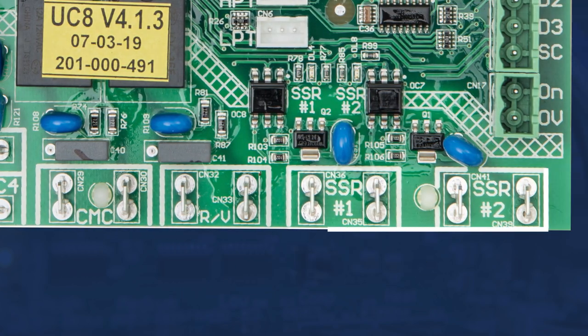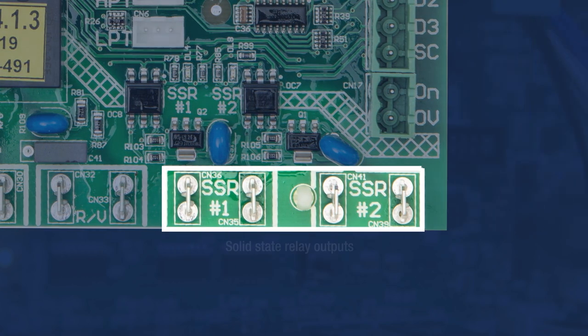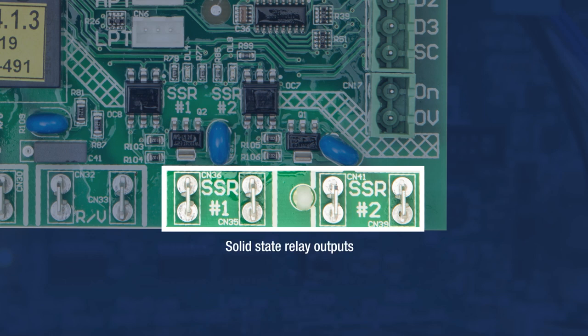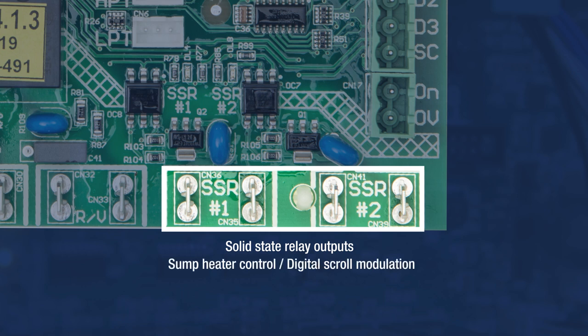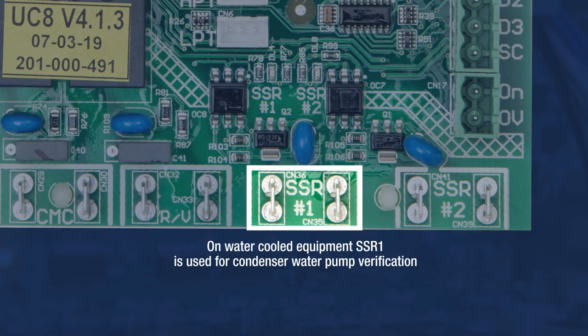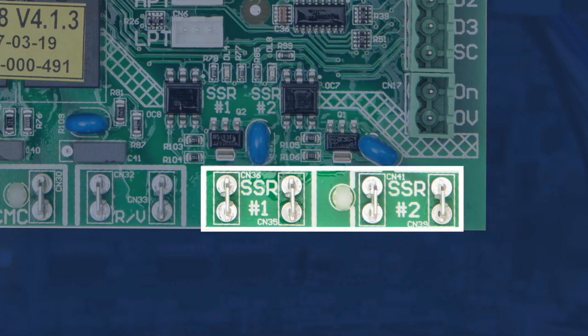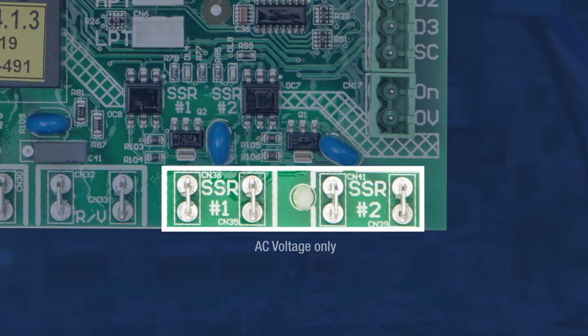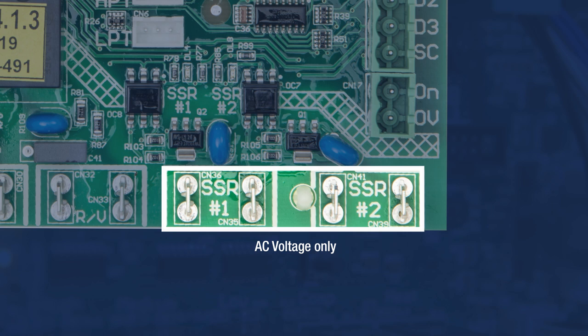SSR1 and SSR2 are solid state relays that can be configured for various uses. They will most likely be utilized for sump heater control and digital scroll modulation. On water-cooled equipment, SSR1 is used for condenser water pump verification. Only AC voltage can be applied to these terminals, as DC voltage used on solid state relays will fail to allow the relay switch to open after it is closed.